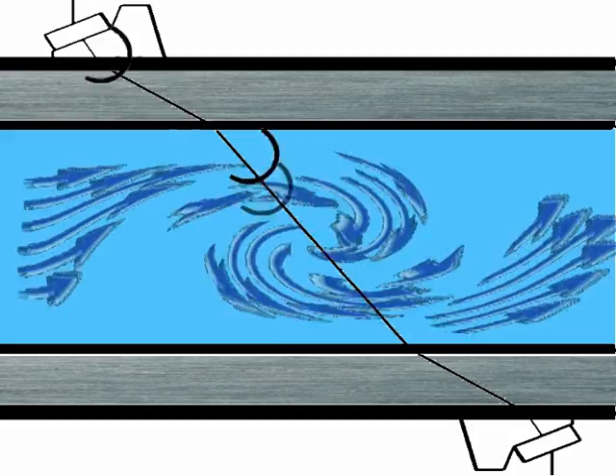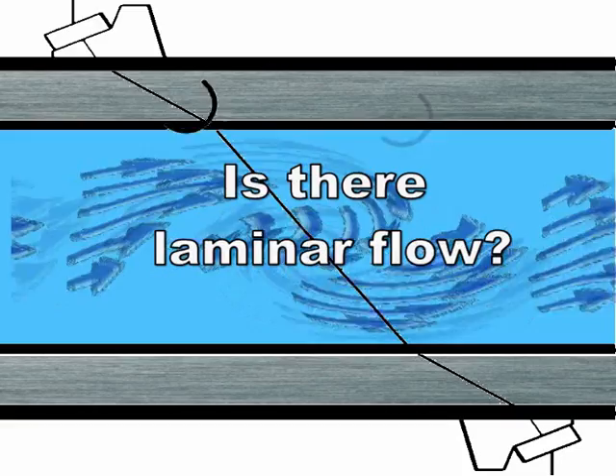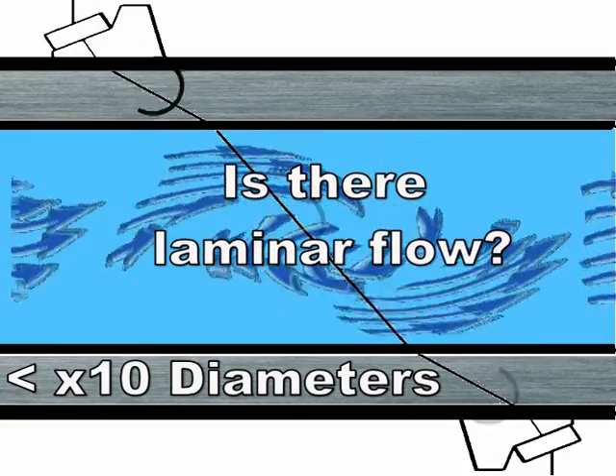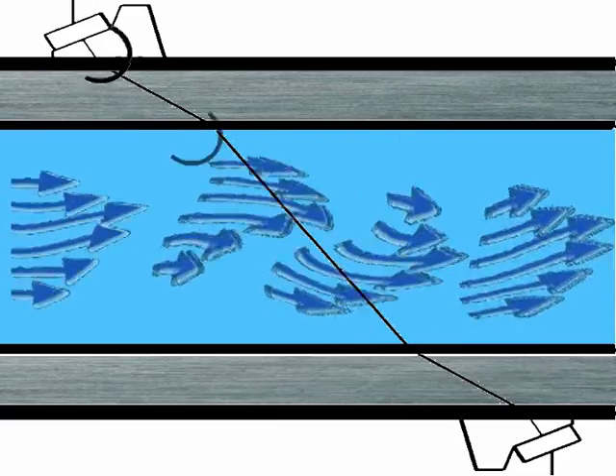Is there laminar flow? Because if it's very disturbed flow, again this will disperse the signal. Typically, you'll have laminar flow when you have 10 diameters upstream and 5 diameters downstream from the flow meter clear of any obstructions.